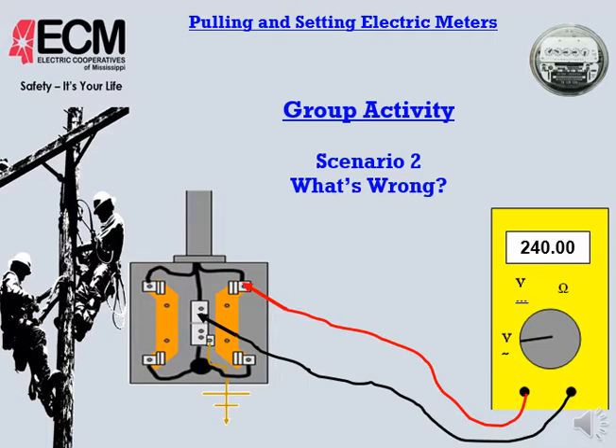Now this could happen anywhere from the transformer down to the meter. A lot of times when we make the connection on the transformer, we could get the neutral and the hot leg crossed. They get squeezed to the wrong lead on the transformer, and that will cause this problem. Or we squeeze it wrong at the weatherhead. Do the same thing at the weatherhead, and it will cause this problem.